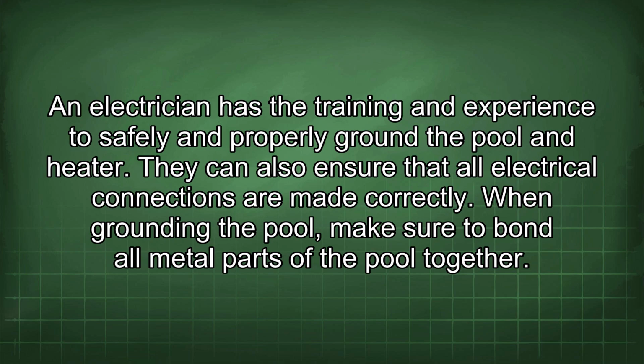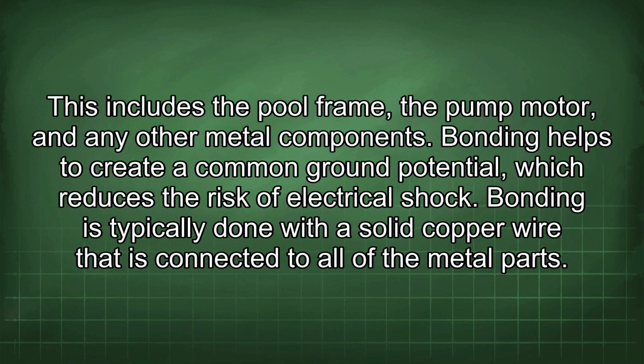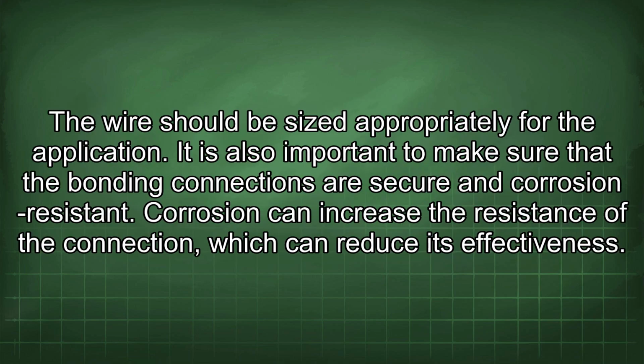When grounding the pool, make sure to bond all metal parts of the pool together. This includes the pool frame, the pump motor, and any other metal components. Bonding helps to create a common ground potential, which reduces the risk of electrical shock. Bonding is typically done with a solid copper wire that is connected to all of the metal parts. The wire should be sized appropriately for the application. It is also important to make sure that the bonding connections are secure and corrosion resistant. Corrosion can increase the resistance of the connection, which can reduce its effectiveness.